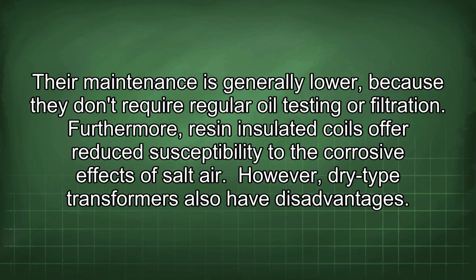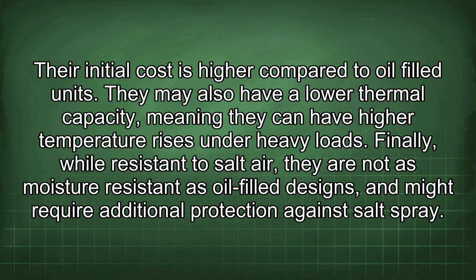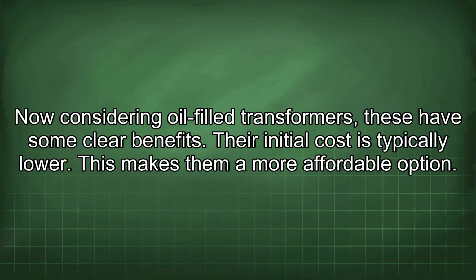However, dry-type transformers also have disadvantages. Their initial cost is higher compared to oil-filled units. They may also have a lower thermal capacity, meaning they can have high temperature rises under heavy loads. Finally, while resistant to salt air, they are not as moisture resistant as oil-filled designs and might require additional protection against salt spray. Now considering oil-filled transformers, these have some clear benefits.